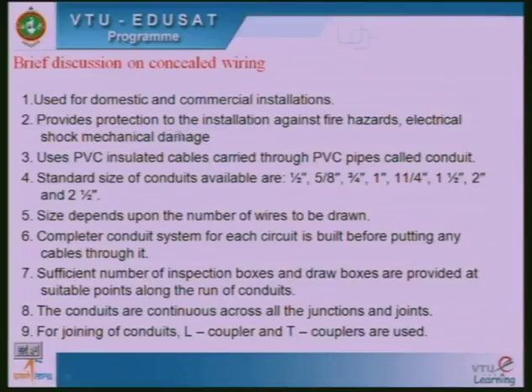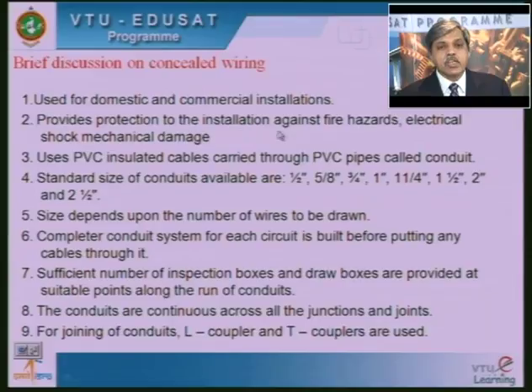Normally this is used for domestic and commercial installations. The second point of this concealed wiring is it provides protection to the installation against the fire hazards, electrical shock, mechanical damage, etc. It uses PVC insulated cables carried through PVC pipes called conduit. There will be PVC pipes depending on the number of conductors or wires it is to carry. These PVC conduits or pipes are available in different sizes, like half inch, 5/8 inch, 3/4 inch, 1 inch, 1 1/4 inch, 1 1/2 inch, 2 inch and 2.5 inches.